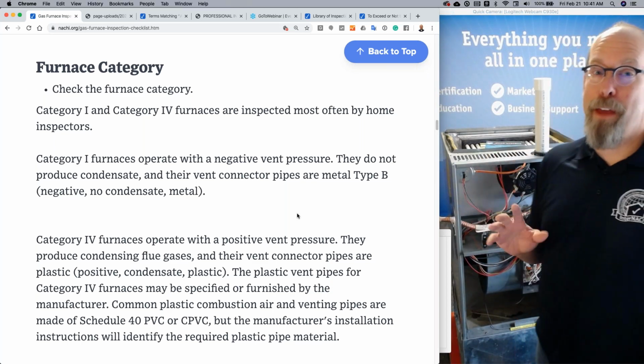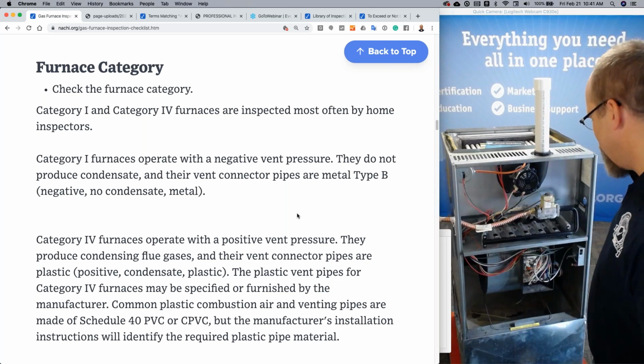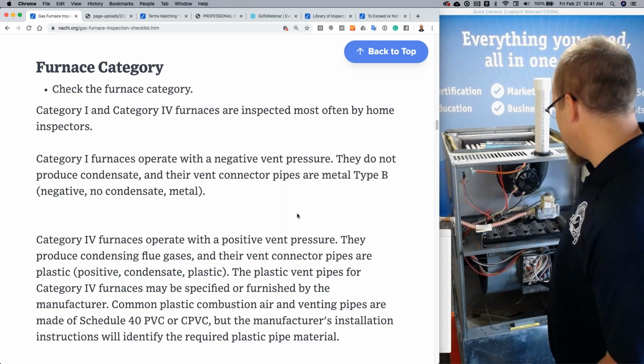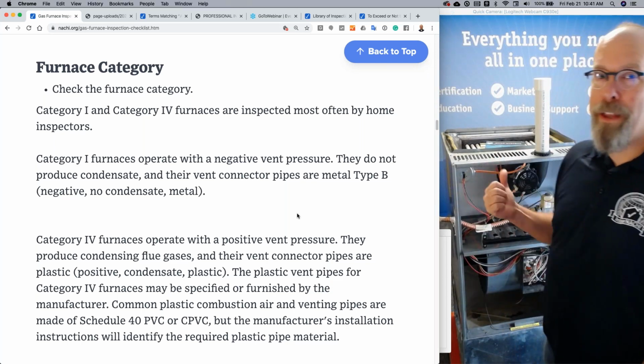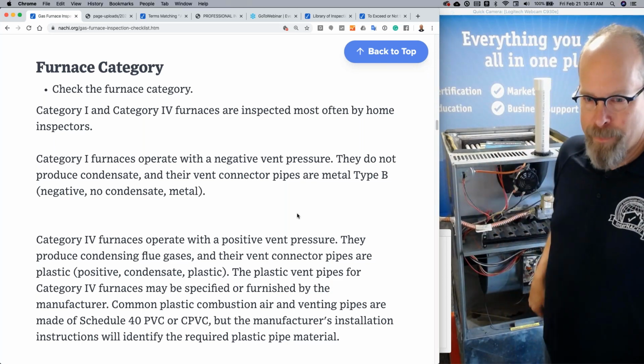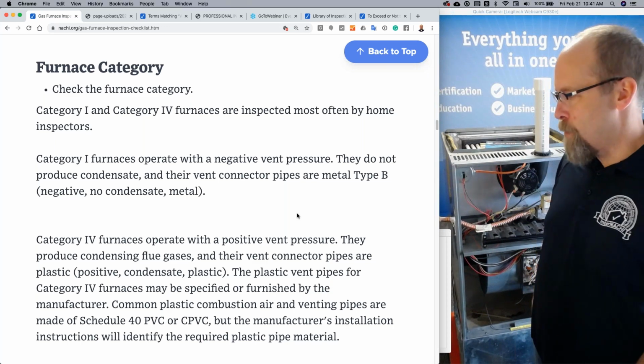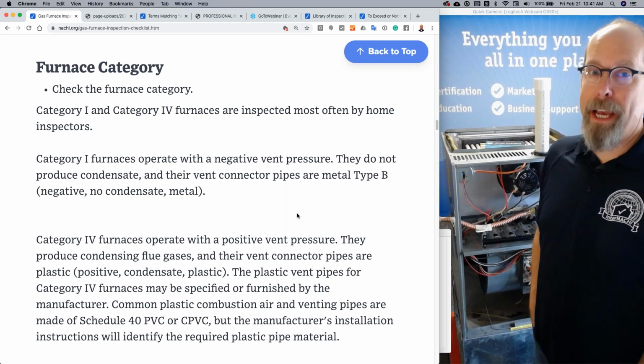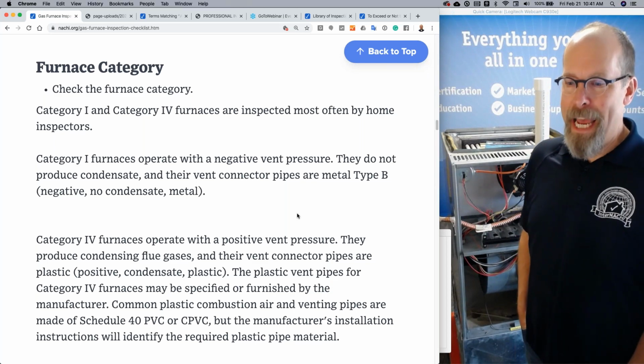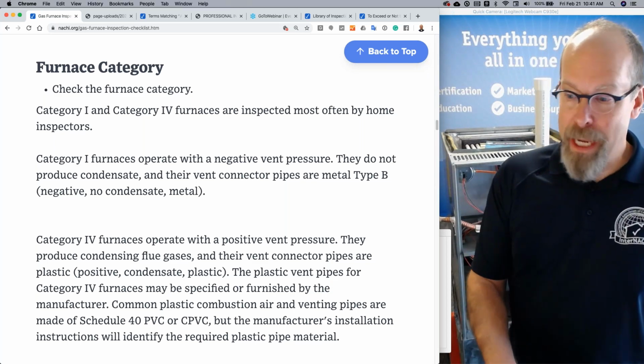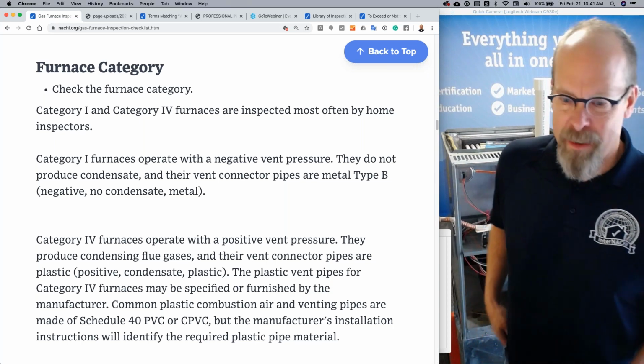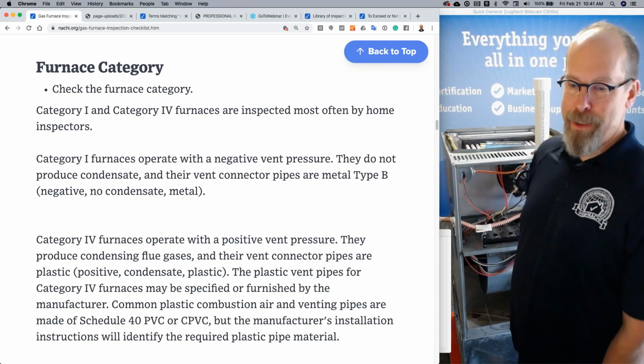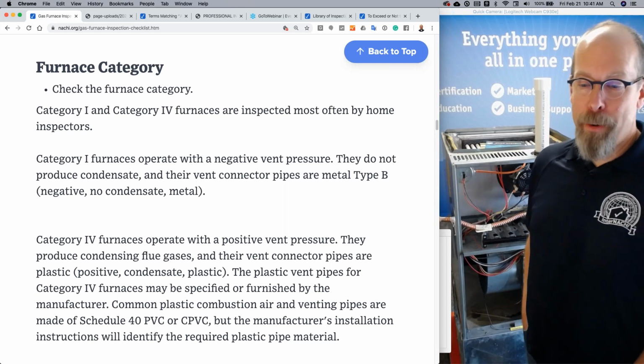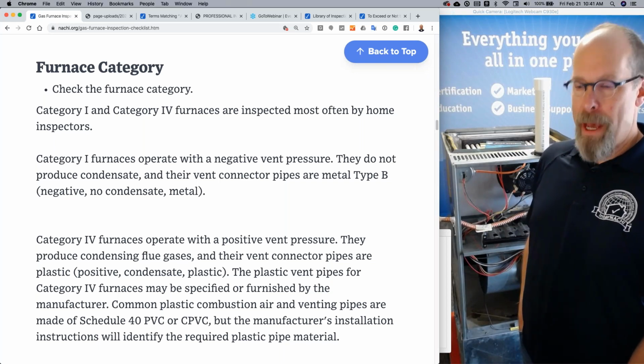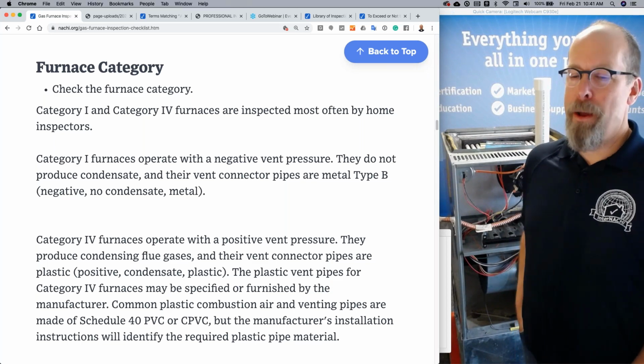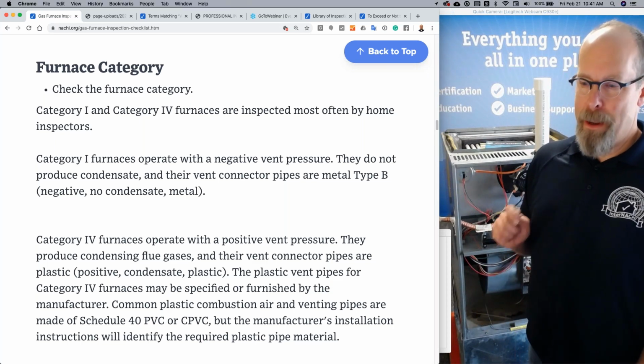So I made some things. You may see some crazy stuff in this furnace just to trick you. There's some tricks here. But what do you think the category is on this one? Well, category 1 and 4 are often inspected by home inspectors, and category 1 furnaces operate with a negative vent pressure. They do not produce condensate, and their vent connector pipes are metal, type B. So category 1, negative, no condensate, metal.